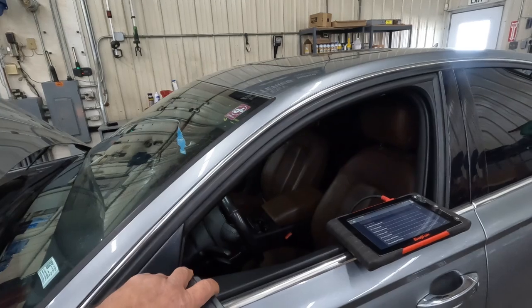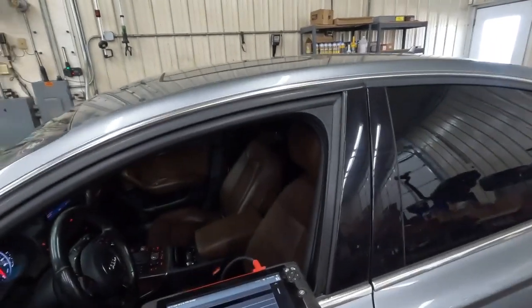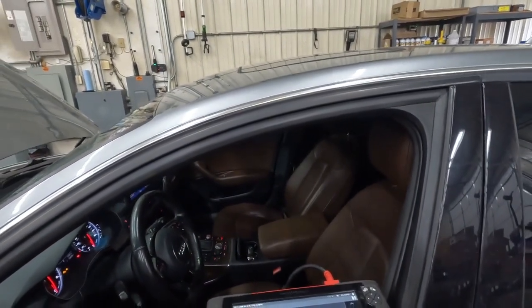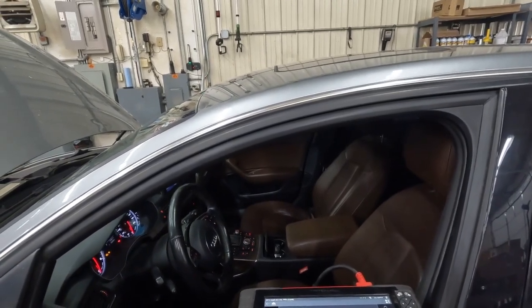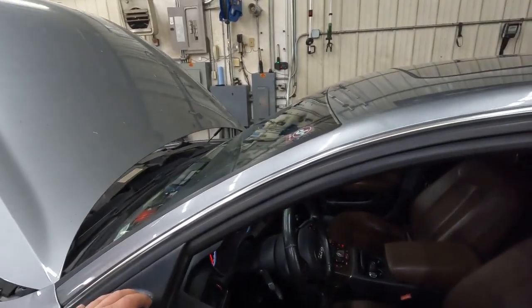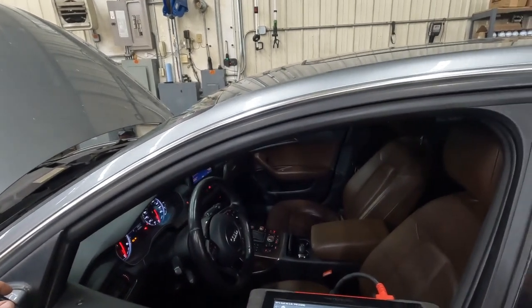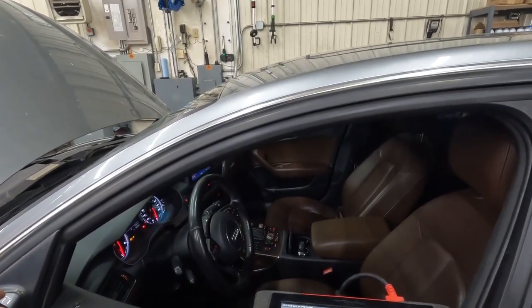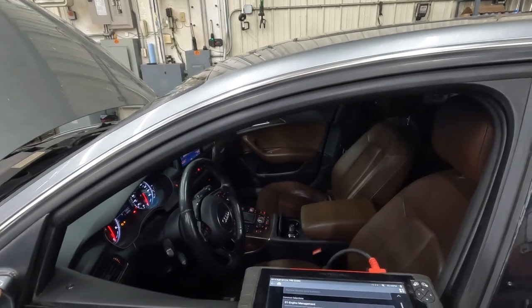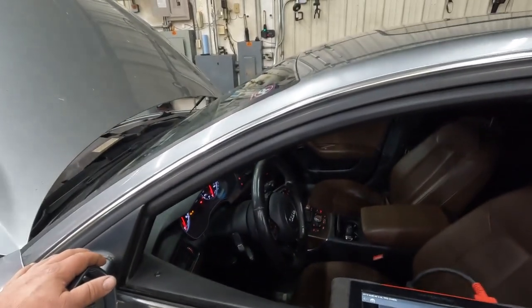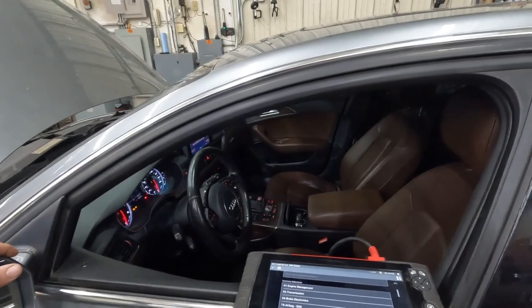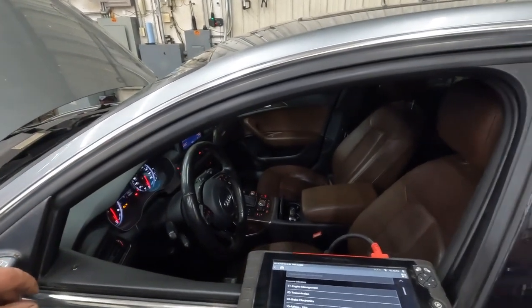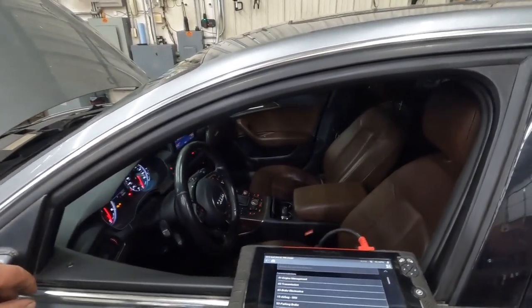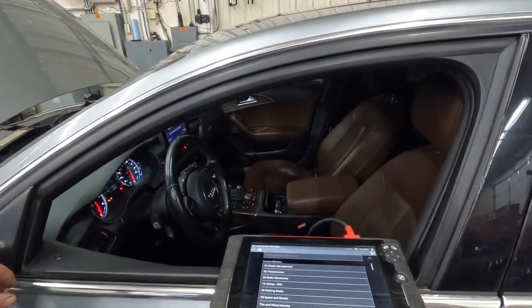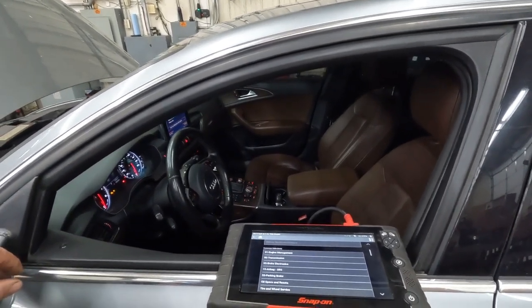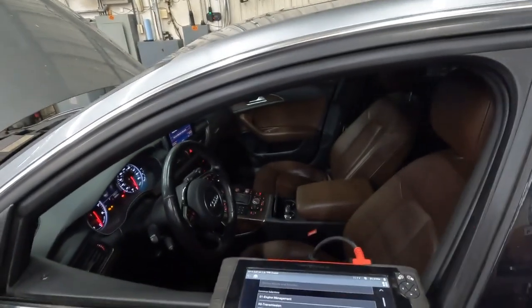Let's see why this thing doesn't work. Usually what I've found on these, there's something prohibiting this from working. I've had cases where somebody replaced the AC compressor and did not do a system learn. Basically the HVAC module needs to see, by readings of some kind, that there's a new compressor in there. I'm not sure what it takes to read that, but it somehow knows you put a new compressor in there, and it doesn't like it, so it'll keep it from running. I don't believe this one's been worked on, though.